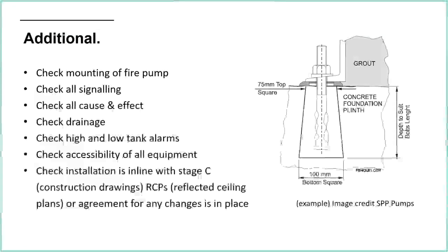Additional things. This is other things to look out for. So, for example, checking the mounting of the fire pump. That's very important. Has the plinth been constructed with the right amount of thickness? Or, if there isn't a plinth, is the floor that the pump is sitting on suitable for the fire pump weight? Do the bolts actually have something to bite into, or are they going through the actual concrete floor? Because this is really important.